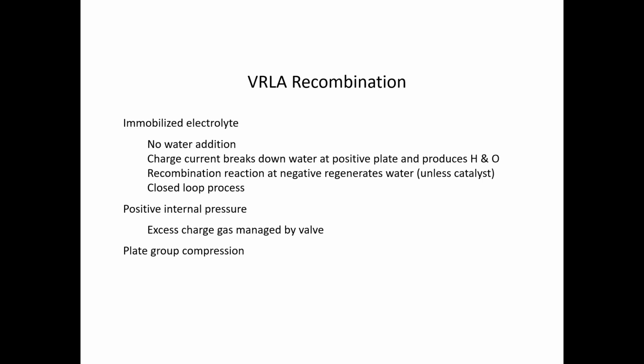Another thing that wasn't really accounted for in the original engineering of these batteries is that hydrogen and oxygen recombining on the negative actually depolarizes the negative. It undercharges the negative. So that's another issue that comes into play with this shorter design life, or design life versus service life. It helps shorten the life of the battery. But it is a closed loop process. And again, the idea is you don't have to periodically add water, and you don't have hydrogen and oxygen just freely venting out of the cell into the room.